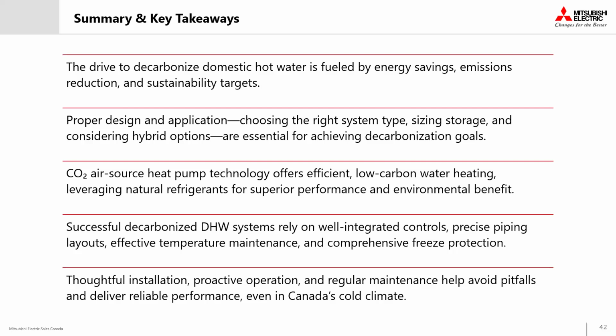And I think the other part of that question was, is glycol recommended in all situations? That really depends on what the designer is comfortable with. If the designer is okay with implementing some sort of heat trace when the ambient temperatures drop quite low and our systems are off, that can be acceptable. But one of the things to consider is that that heat trace will likely need to be on backup power if it's used. So there are a few other factors to consider there. From what we've seen, the most common form of freeze protection is glycol. A lot of the CO2-based heat pump water heaters are approved to use glycol solution. So that's probably the most common one that we see.